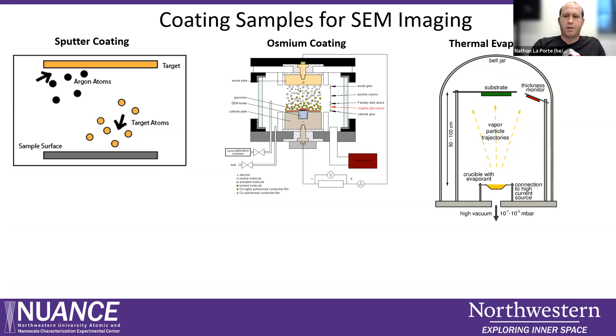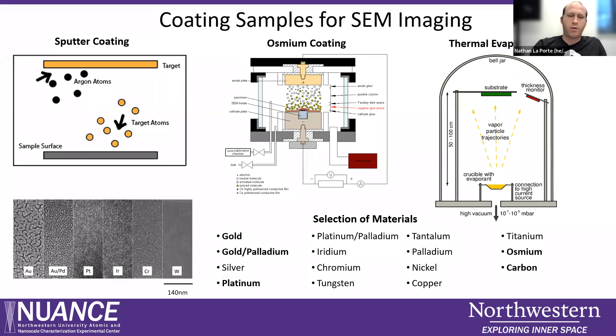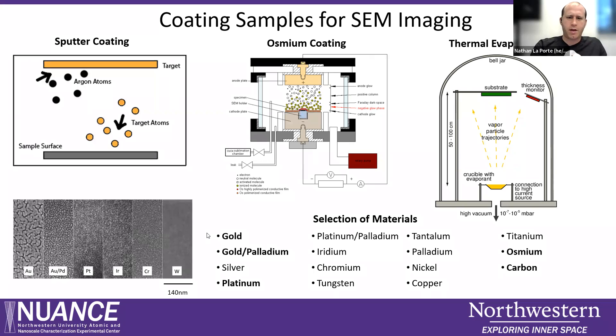Similar to the sputter coater, the thermal evaporator is not going to give you a coating around all the sides of your sample — it's basically going to coat the face of your sample that is facing the crucible. So it's not a great choice if your sample is highly porous or has a lot of surface area or is a weird shape. What's nice about the thermal evaporator is it has the widest range of materials you can use, because basically anything that melts and evaporates you can use, and you don't have to buy a big, thick sputter target for hundreds or thousands of dollars — you can use a couple of pellets of whatever material it is. Carbon coating also takes place in the sputter coater machine, but it's actually a thermal evaporation of carbon using a pair of carbon rods. There's an electrical discharge between them that sprays off carbon particles everywhere, including on your sample.